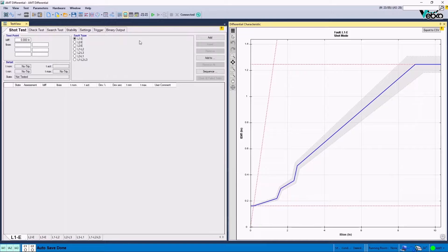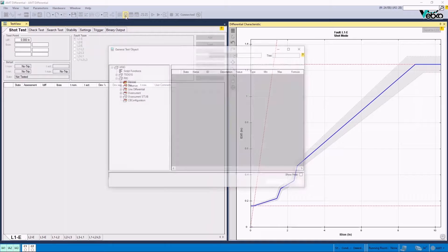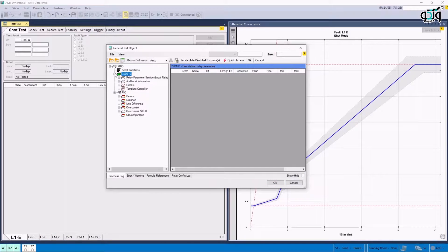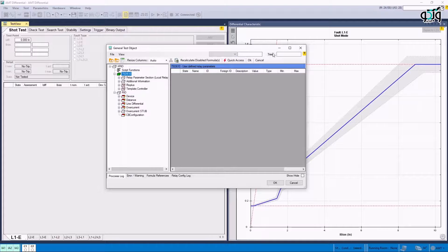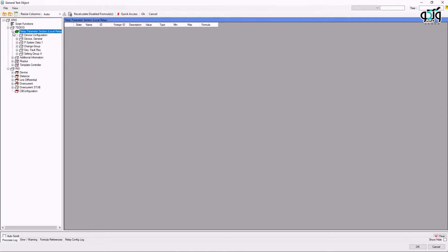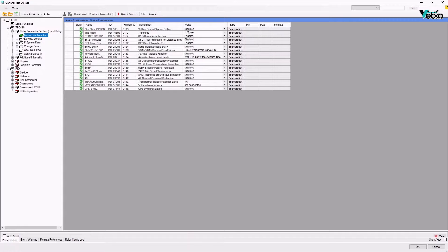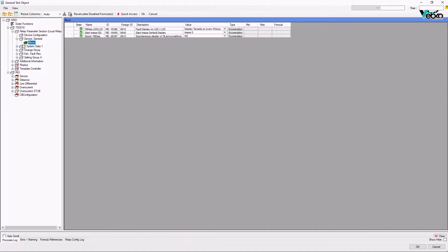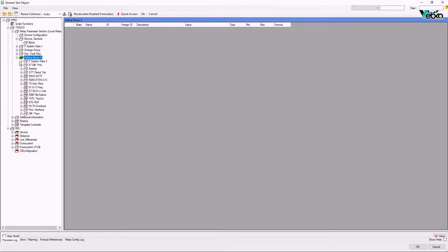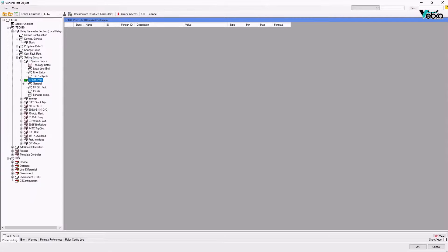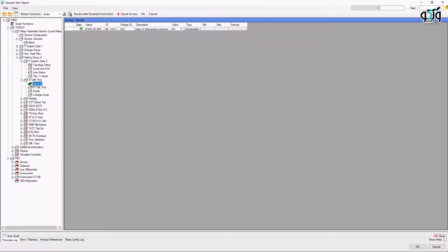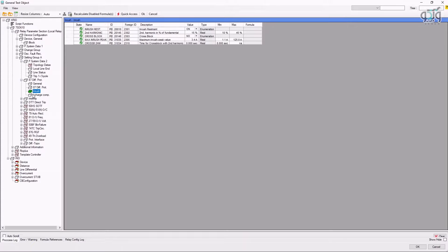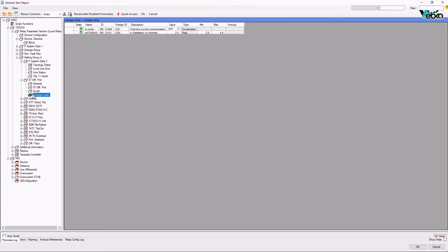Before beginning the test, the test object parameters window is opened again and 7SD610 subcategory is opened by clicking on the plus sign. In Relay Parameters section, it is possible to view the information related to the local relay or the current post in different subcategories. In Subcategory Setting Group A, it is possible to view the setting of different functions. By going to Subcategory 87 DIFF Prot, it is possible to examine the activity status of this parameter, time and current settings of pickup and trip, the inrush settings, and the parameter related to the charge of the line.